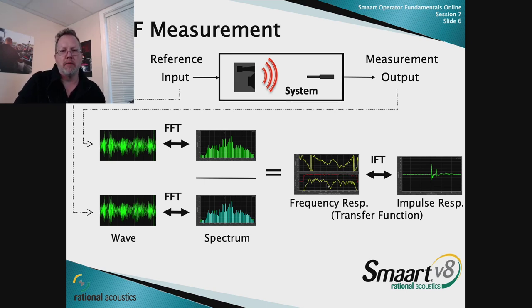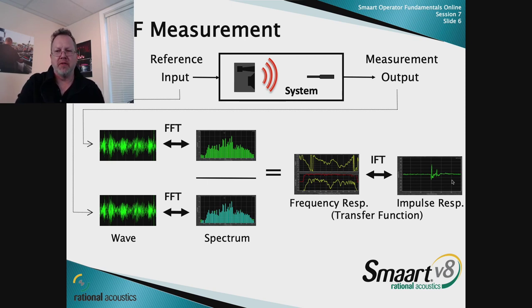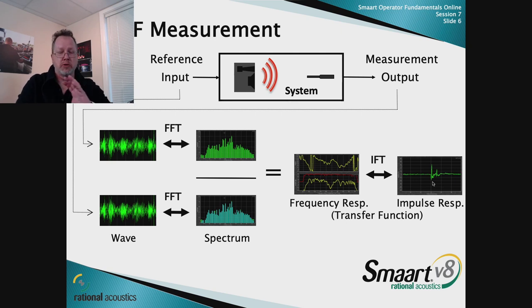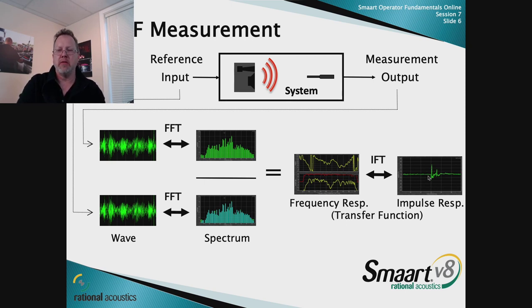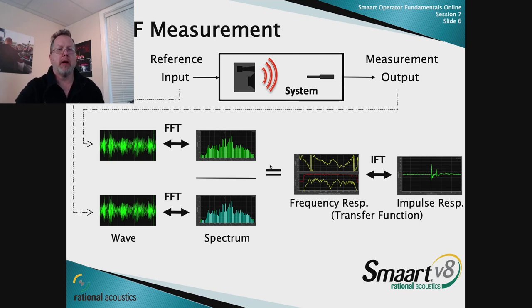We start with single-channel time domain — the waveform — run an FFT to get the single-channel spectra in frequency domain, do the transfer function to get the frequency response in magnitude and phase by frequency, then run an IFT to get the time domain view of the system response. This data and that data are literally the exact same data — just viewed differently. The measurement engine runs this complete cycle 24 times a second.